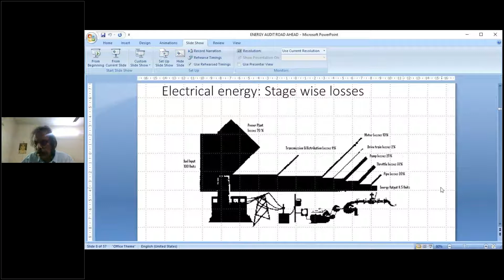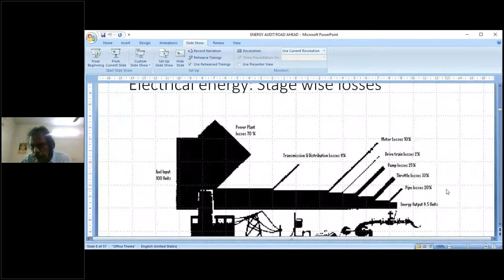Then you see that water usage is very high - we don't want so much water, we want to reduce the water flow. So we throttle the outlet of the pump. In throttling, by closing the valve, you lose about 33%. Then the friction losses in the pipe are about 20%. So ultimately, what reaches the overhead tank is 9.5 units. So the efficiency - if you see what is the energy in the overhead tank water versus the energy input to the power plant - it is only 9.5%, 9.5 by 100.